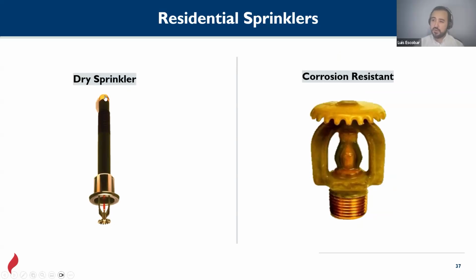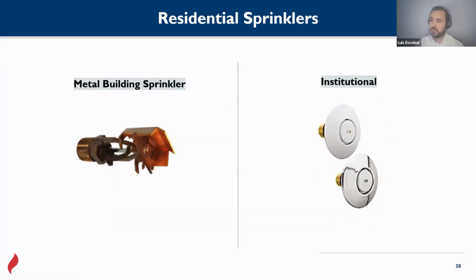This is a dry system. For example, if we have a wet system on the ceiling, but we have a cooler, we can have a piping drop and install that sprinkler, which has a dry barrel length here, so the water is not going to freeze. And we'll make sure the protection is taken care of in that cooler, just as an example. And corrosion resistant sprinklers, as we mentioned, are for outdoor areas or corrosive environments. Then there are metal building sprinklers and institutional sprinklers, which are for mental health occupancies where people could use the sprinkler to harm themselves or something similar. So there is a vast quantity of sprinklers for that.